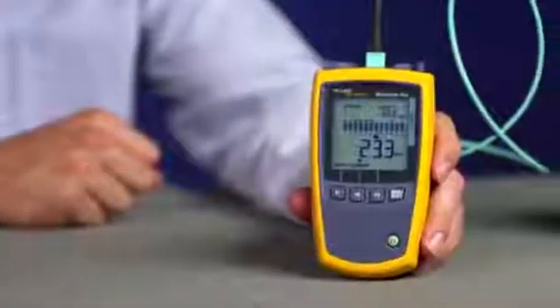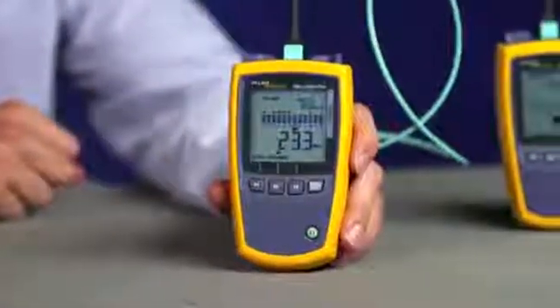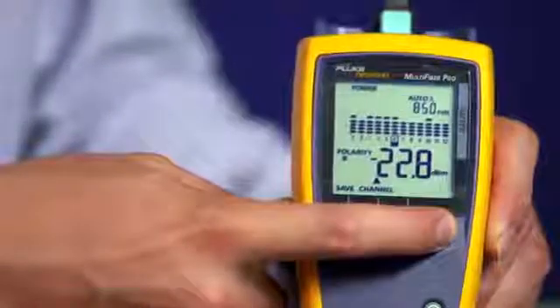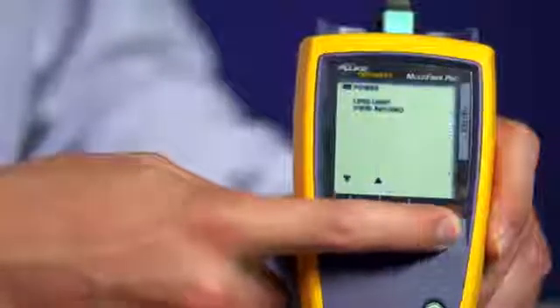After you've set the reference with the supplied MPO test cords, make sure you use the correct loss limit. Press MENU for 3 seconds, then use the arrow keys to move to loss limit.